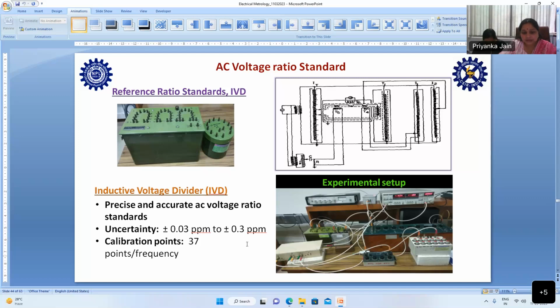Its uncertainty is in the range of 0.03 ppm to 0.3 ppm, and it has 37 calibration points if you are comparing for first, second, third decades and last combination decades. If ERTL persons are there, they must have heard about this because they are coming to us for the calibration of inductive voltage dividers. Here you can see this is the inductive voltage divider. This is our reference AC voltage ratio standard, and this is our experimental setup to define the accuracy and precision of the inductive voltage divider.